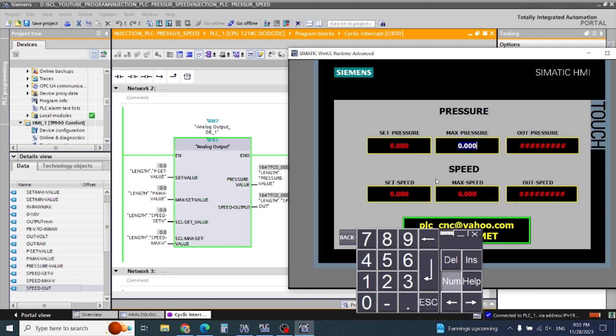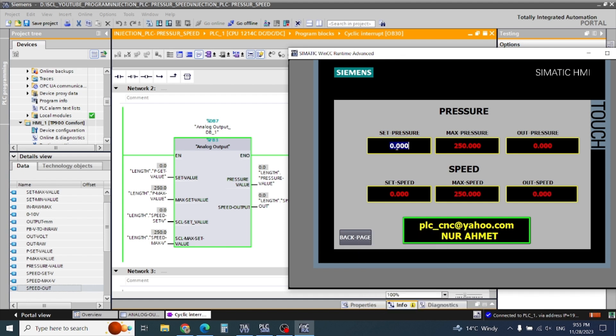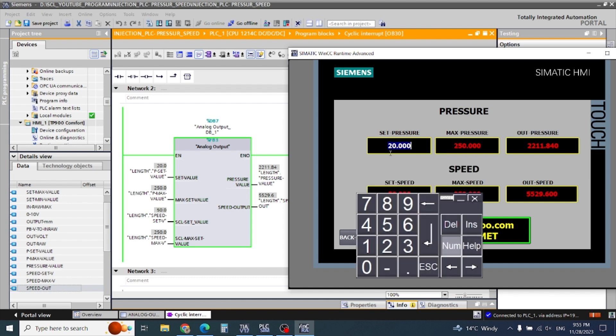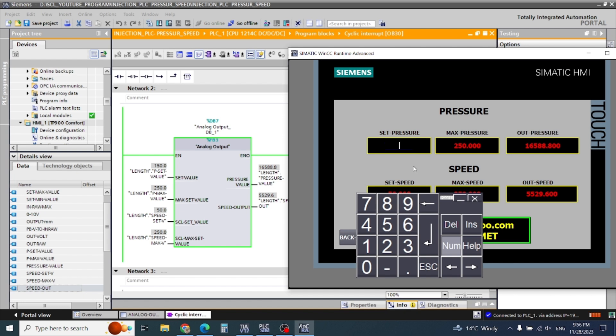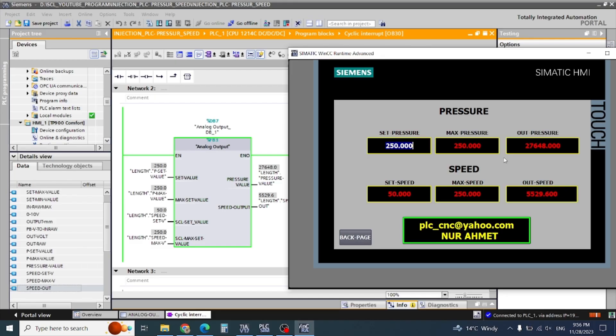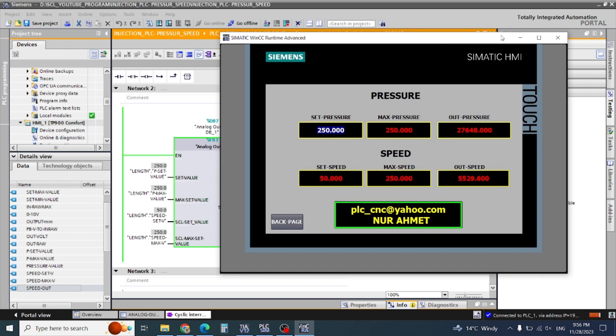First I will fix my maximum pressure — suppose 250 bar — and speed 250. If I check my pressure is 20, this is our engineering value output coming. Now here is 50. Let's make it 150, and when we give 250 the engineering value means 10 volt or 20 milliampere output will come when you write the program.